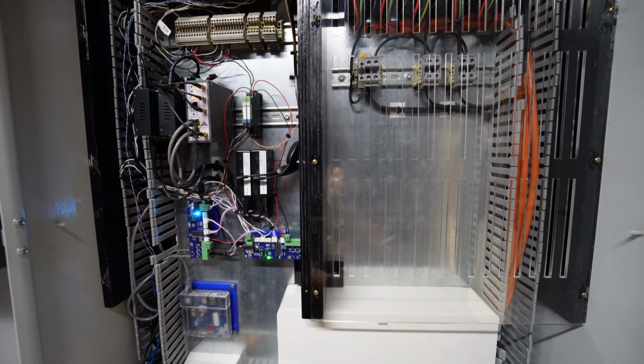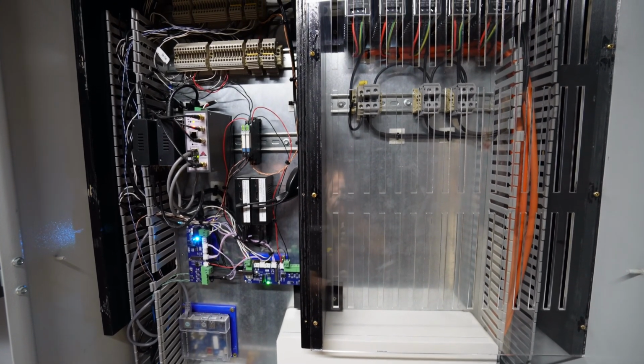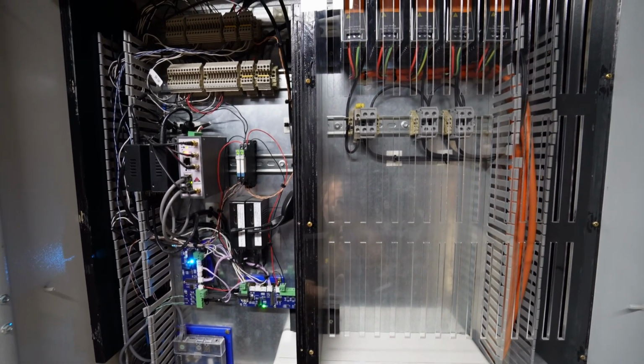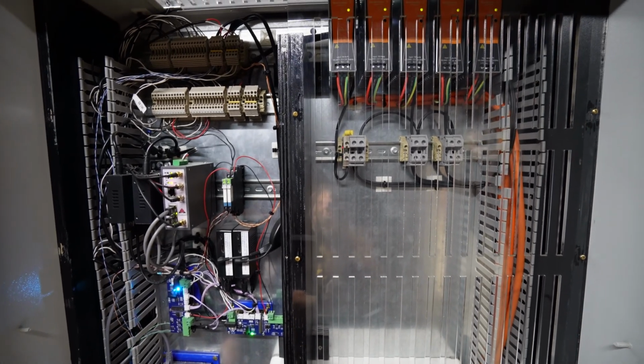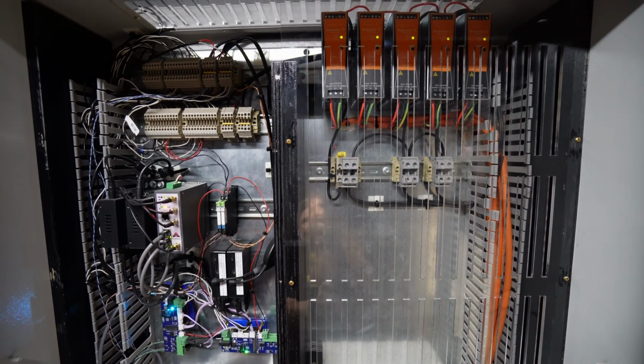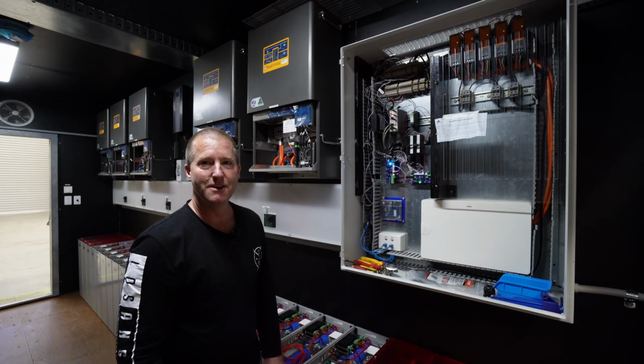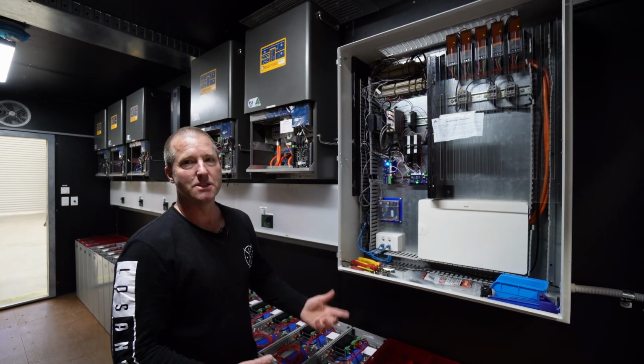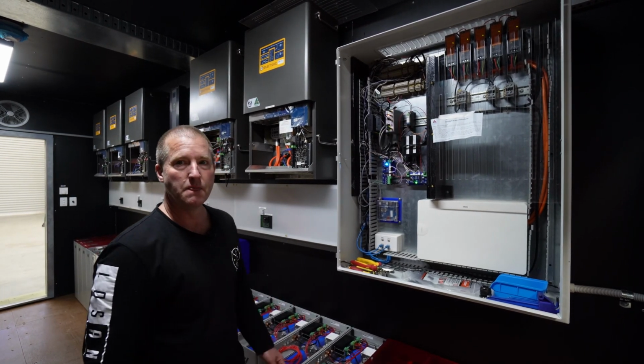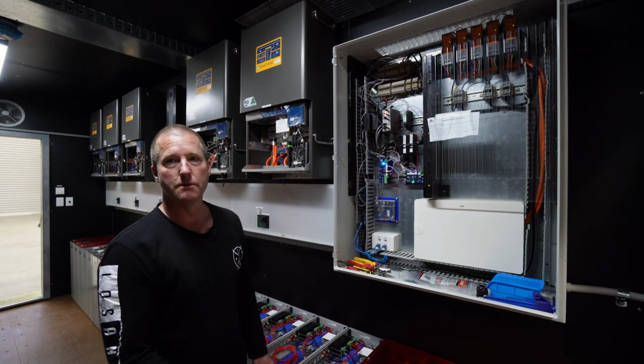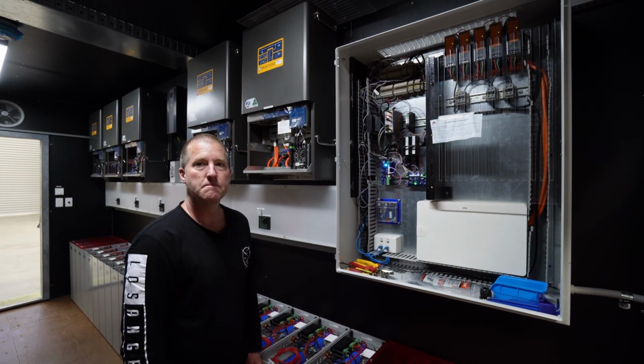At the top here we've got 5 power supplies in series that produce 145 volts, so we can charge the system off grid power to bring the batteries up in case everything went off. If you shipped it somewhere and it got stuck in transit and everything went flat, you could recover it just with a generator or a main supply. So you've actually got multiple redundancies.